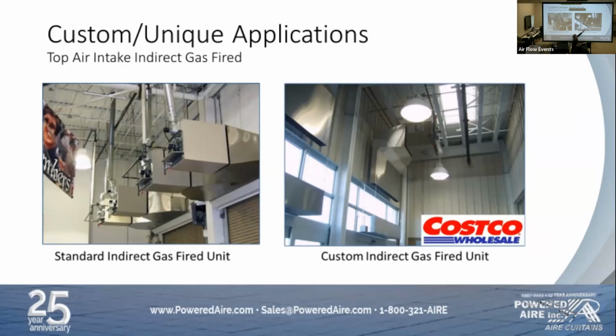So what we did, this is our air curtain. It's a top air intake. So normally you would have a front intake. We switched it to top. We put a 90-degree bend in the transition. We were able to raise it up so we could now mount the indirect gas heater and the transition up at the ceiling. So you still have the benefits. It's just kind of a different configuration.